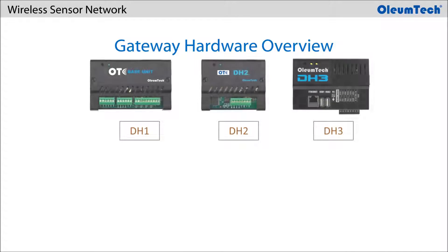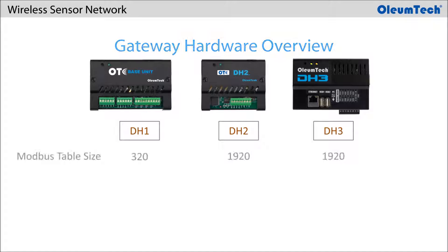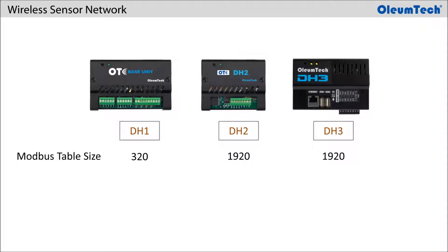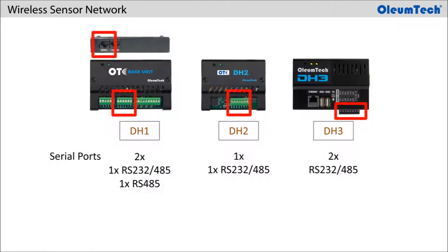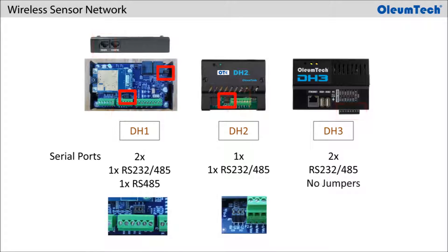Let's get more familiar with the OTC gateways by first going over the differences. The DH2 and DH3 have the larger Modbus holding register table size. The DH1 has two serial ports, the DH2 has one, and the DH3 has two serial ports that can be configured just with the Breeze software. The other two gateways require modifying the jumper settings.